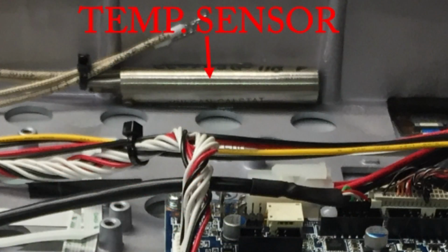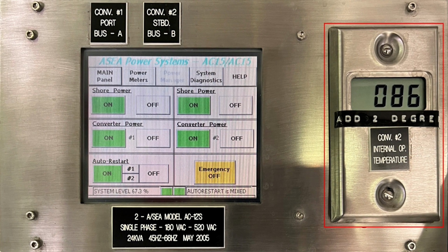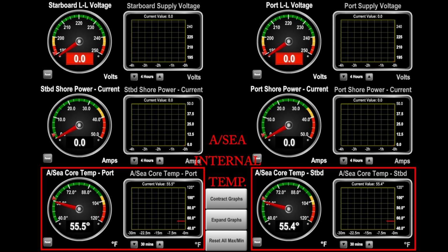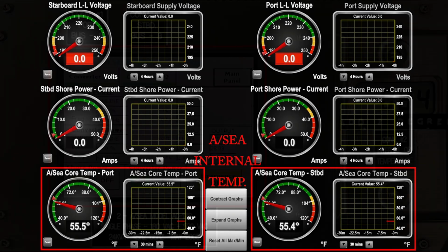It's also a good idea to install internal remote temperature probes, preferably where you can set high temperature alarm points, to correct any ventilation issues before the unit's self-protection circuitry shuts the unit off.